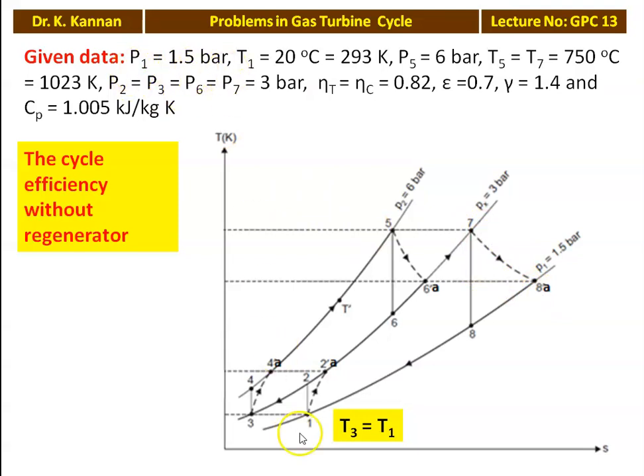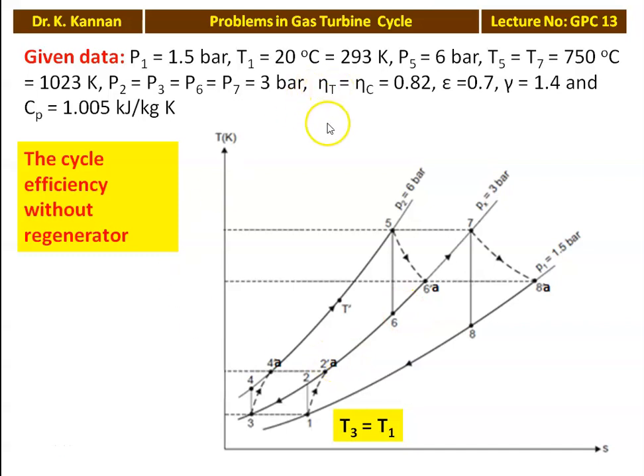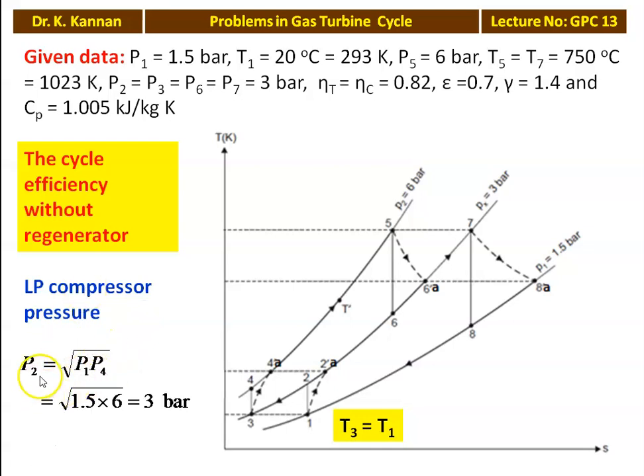Turbine efficiency and compressor efficiency are equal to 0.82, effectiveness of heat exchanger is 0.7, gamma equal to 1.4, and Cp equal to 1.005. The intermediate compressor pressure: P2 equal to square root of P1 into P4, which is square root of 1.5 into 6, equal to 3 bar. In this cycle we calculate temperatures T2A, T4A, T6A, and T8A using the isentropic compression and expansion expressions, then calculate turbine work, compressor work input, heat supply, and cycle efficiency. For the LP compressor: T2 equal to T1 into (P2/P1) to the power (gamma minus 1)/gamma, which is 293 into (3/1.5) to the power (1.4 minus 1)/1.4 equal to 357.2 Kelvin. Using compressor efficiency: T2A equal to T1 plus (T2 minus T1) divided by eta_C, which is 293 plus (357.2 minus 293) divided by 0.82 equal to 371.3 Kelvin.